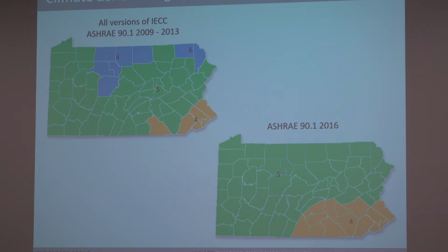I don't know how Pennsylvania and Philadelphia will adopt these, but I will say that the 2018 IECC, which goes along with ASHRAE 2016, they've adopted different climate. The IECC 2018 hasn't adopted the new climate zone map, whereas ASHRAE has. So hopefully we'll get a little bit better clarification in the local jurisdiction from that. Otherwise, depending on which compliance path you choose, IECC or ASHRAE, you may be in a slightly different climate zone. But you'll see that that whole southern part of Pennsylvania, a whole bunch of new counties have been added to Zone 4.